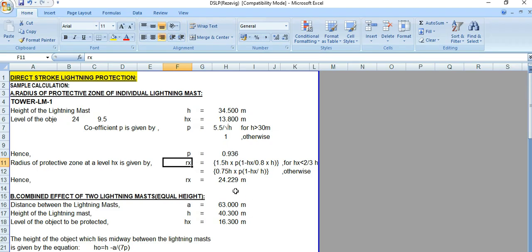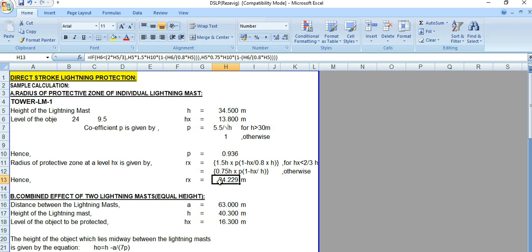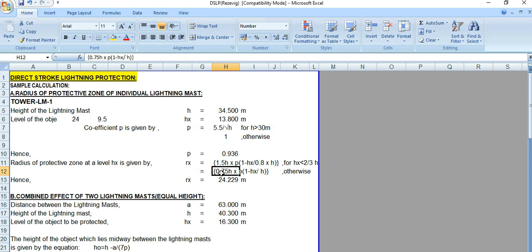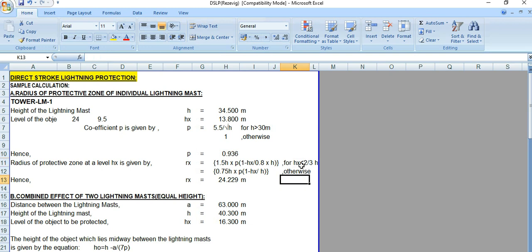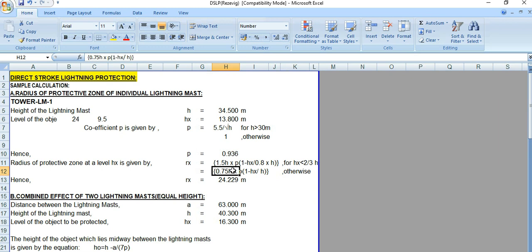Using this formula, the value of rx comes out to 24.229 meters. These two equations are the main formulas to calculate the radius of the protection zone. We need to check whether hx is less than two-thirds of h or not — if yes, follow the first equation; otherwise use the second equation.